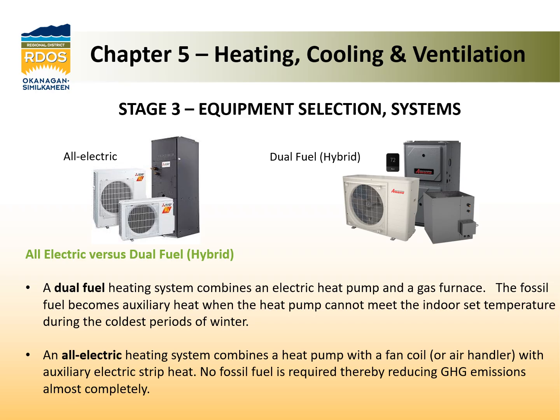The all-electric will include the outdoor compressor, the indoor coil, and, if necessary, auxiliary heat provided by electric strip. If the heat pump can't keep up during the coldest winter peaks, the electric strip will come on and top up the heat pump. The dual fuel is typically a heat pump coupled with a gas boiler or gas furnace. The indoor coil is separately attached to the furnace. In this case, when the heat pump can't keep up during those winter peaks, the gas furnace will take over completely.